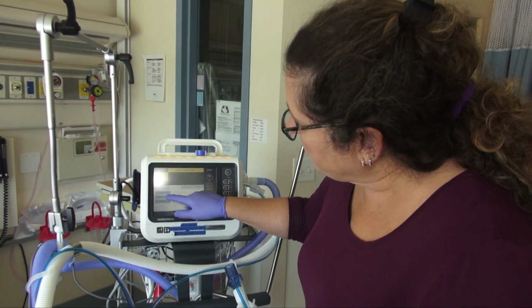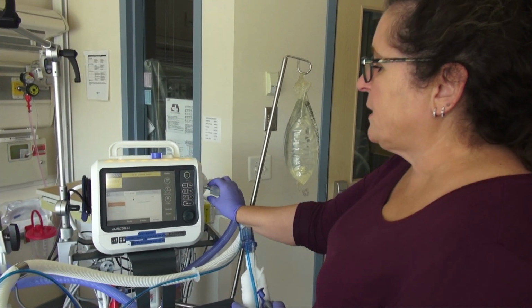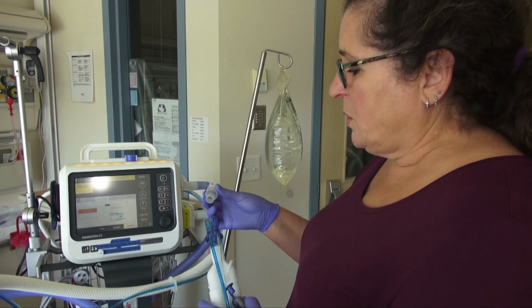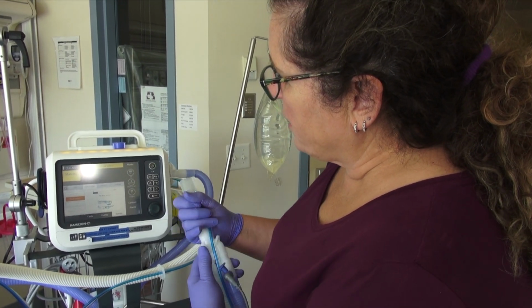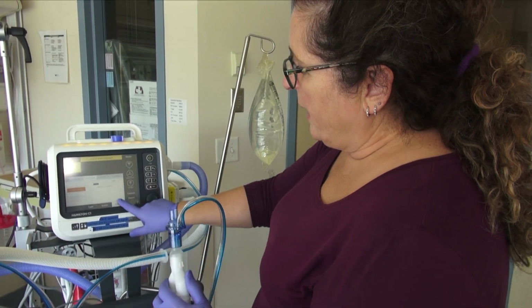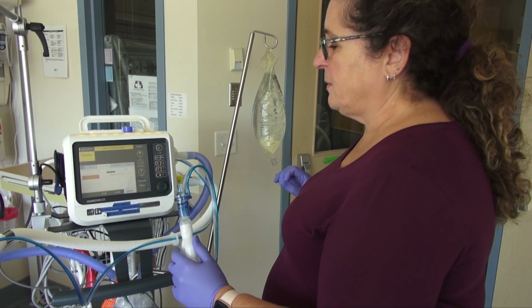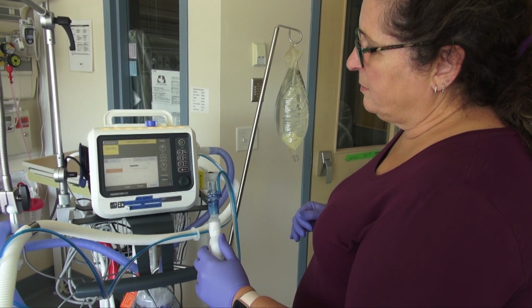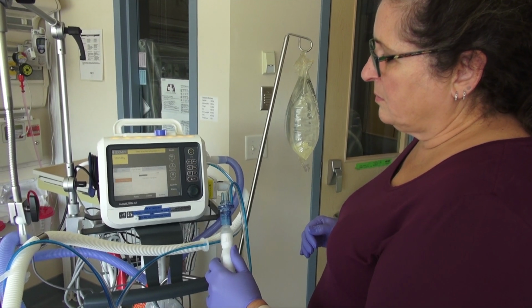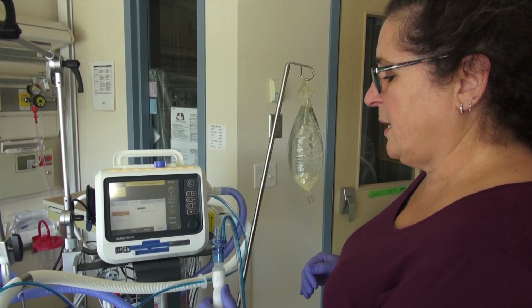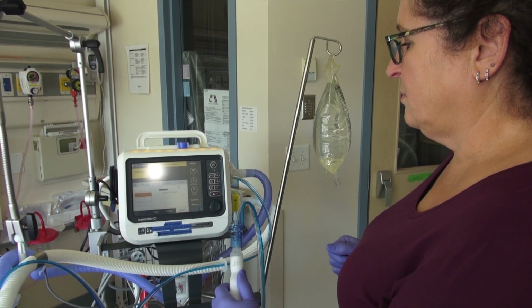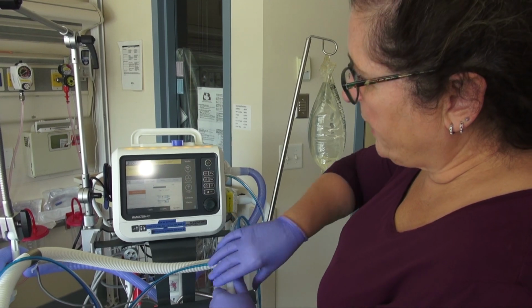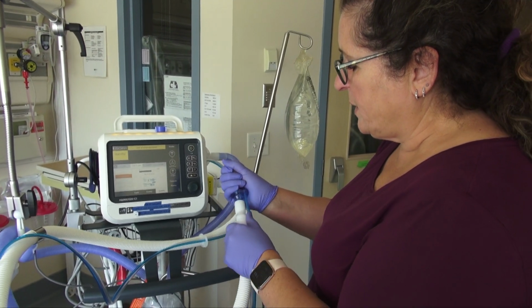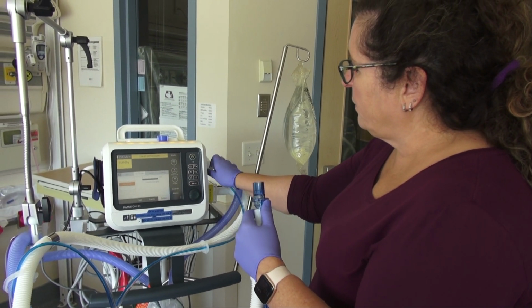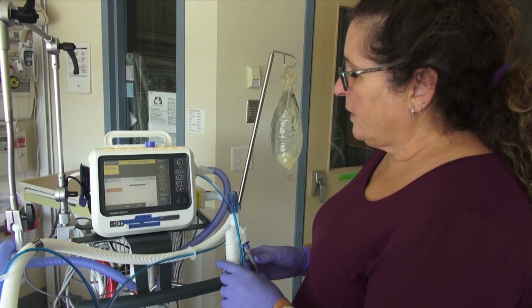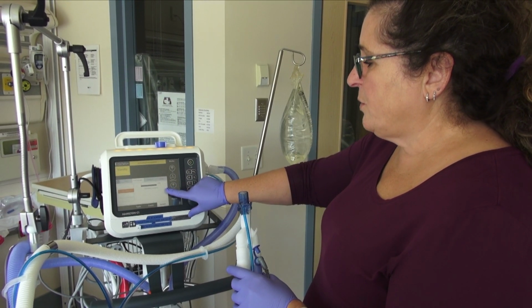Second test going down is your flow sensor test. Again, it tells you to disconnect the patient circuit. This is where you're going to get your little piece that inserts here to flip the flow sensor as it shows on the screen. Once you've done that, it will go through its calibration process and give you instructions once it's done this side. Okay, now it tells you to flip the flow sensor back the way it was in the first place and take out the little flow sensor adapter. It will continue to finish off its calibration as you can see on the screen.